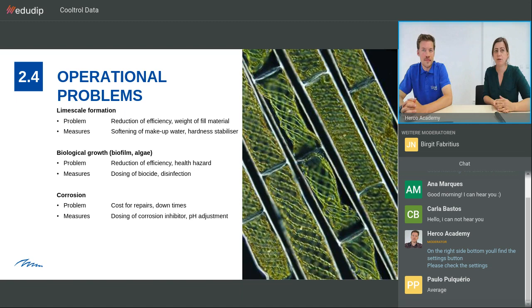Measures, very simple, usually it's dosing of a biocide. It can also be disinfection with UV, but the most common method is biocide dosing. Corrosion can be a problem if there is an elevated concentration of chlorine, of sulfate, if the pH is out of a, let's say, more or less neutral range. And this results in leaks, so that there are costs for repairs, there is downtime of the whole system.